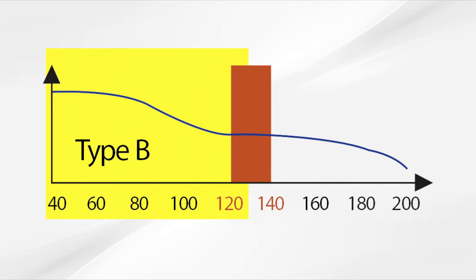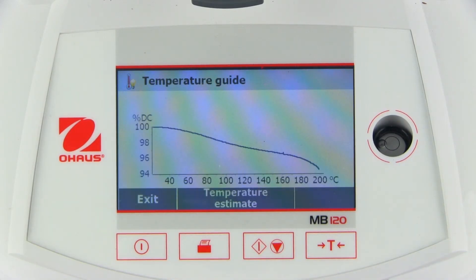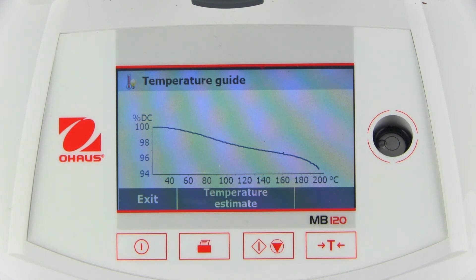In the second instance, the sample will dry at a certain temperature. Then at some point, the sample will burn or decompose, indicating a secondary weight loss phase. The optimum drying temperature for the sample will be where the weight loss plateaus after the initial drying phase. In this example, the sample under test reaches the end of the drying phase at around 150 degrees Celsius before it begins to burn. This is the appropriate drying temperature that should be used in a method for this particular sample.